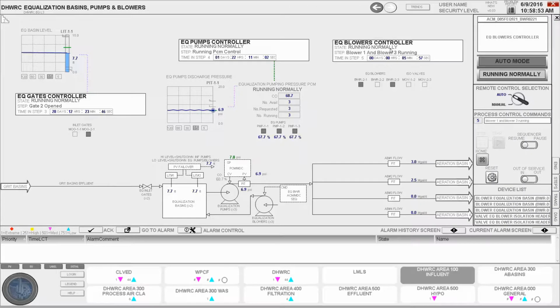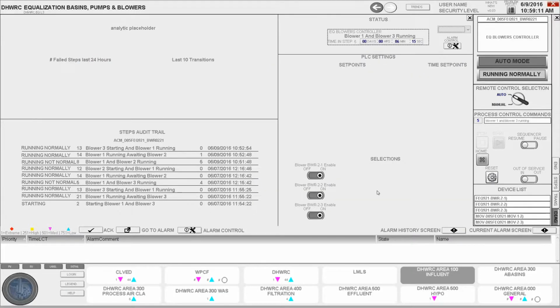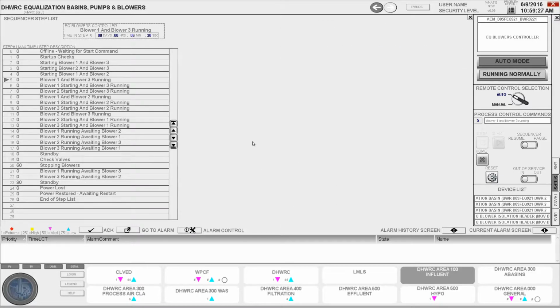By selecting the PIQ, the Device Control Interface, DCI, opens up to the right. Here we can put the PIQ in either auto or manual. Here are the manual controls and the out of service toggle. For further information, we can select the Diagnostic tab. The Audit Trail shows the last 10 steps, the PLC setting for set points and time set points, and this area is for the control toggles. Next we select the Steps tab, which displays all the available steps for this PIQ. The true brains of the PIQ reside in the Transitions tab.